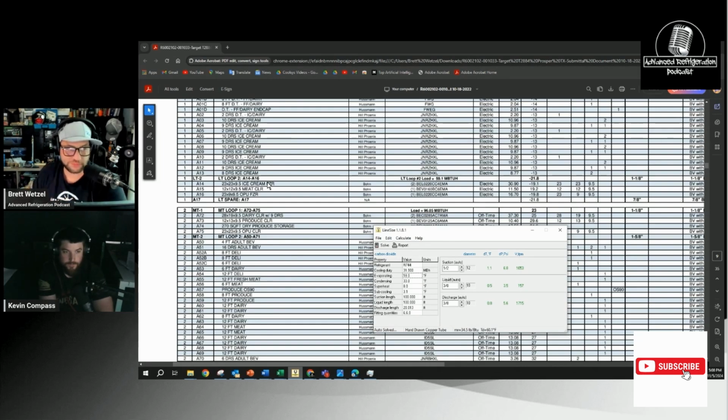Yeah. If you lower the superheat, you would get essentially a lower TD, and then with everything just cycling off and on, you get more mass flow back to the compressors and have nice cool compressors. I'm never gonna like pulse valves. I'm not a fan either. You do not get the performance you do out of a stepper.